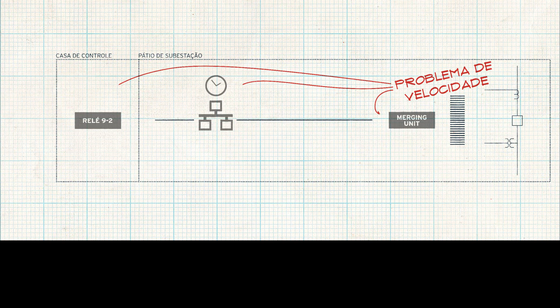There's an Ethernet network that's now out in my yard, and it can extend your electronic security perimeter beyond the control house out into the yard, so it becomes a security problem. The other challenge is that I've gone from 1 or maybe 2 electronic devices to maybe as many as 7 to do your protection, and if any one of those fails, you no longer have any protection. So now I've got a reliability problem. And then finally, I've got to get signals from the merging unit back to my relay. I've got to digitize them, move them through a network, and then digest them over here, and I take a speed hit. So the other problem is speed.